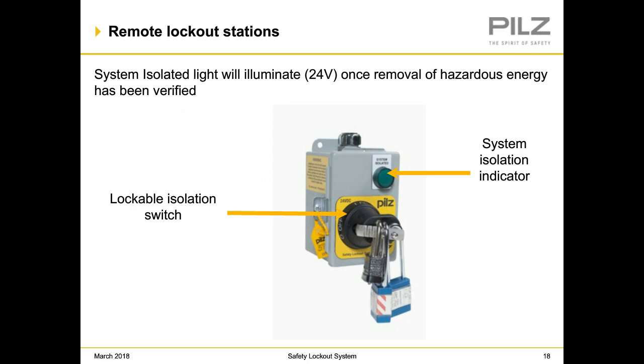And then you have your remote lockout stations. A system isolated light will illuminate once removal of hazardous energy has been verified. And you'll see you have a lockable isolation switch here that you turn off, and then you wait for that light to come on. And that light will either come on almost immediately, or if you're waiting for a zero speed monitor or something like that, it might be delayed in coming on because, again, you have maybe a standstill or zero speed monitor that is signaling to the safety PLC.